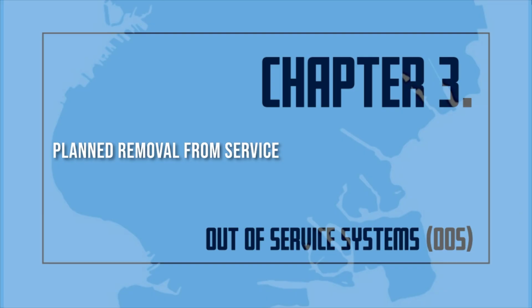Notify the fire department in accordance with Fire Code 901.7.5 if required. Notify the responsible person, designated by the owner, to issue hot work authorizations in accordance with Fire Code, Chapter 26. Notify the central station and insurance carrier. Notify the occupants in the affected areas if the duration of time the sprinkler system or the fire alarm system will be out of service is estimated to be more than 30 minutes. Place a tag at each fire department connection, standpipe, and sprinkler system control valve and fire command center, indicating which fire protection system or part thereof is out of service. Maintain the fire protection system in service until work is ready to begin.